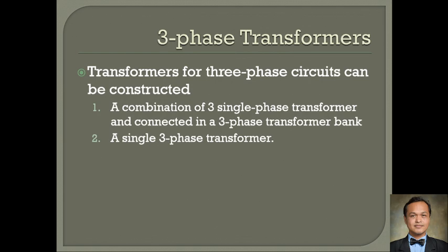While with a single three-phase transformer, if there is an unbalanced voltage in the system, the whole three-phase transformer will be replaced. Another thing is the weight of the transformer. The single three-phase transformer is much heavier than three single-phase transformers.